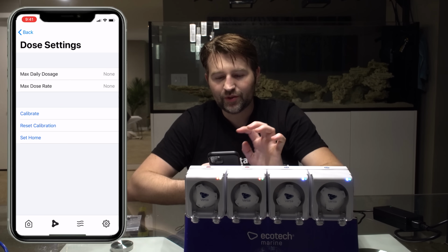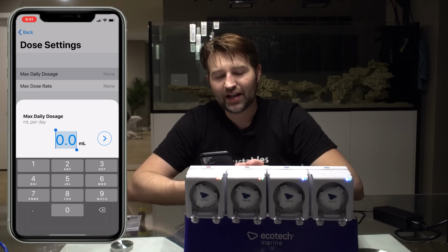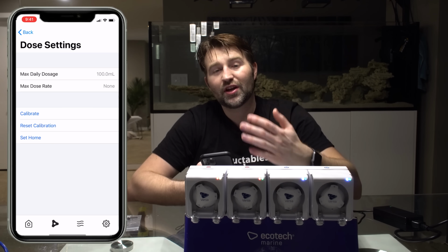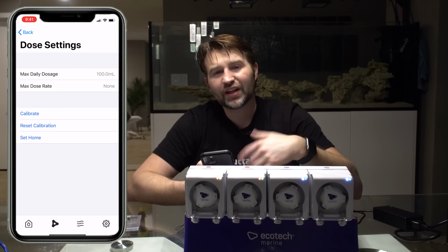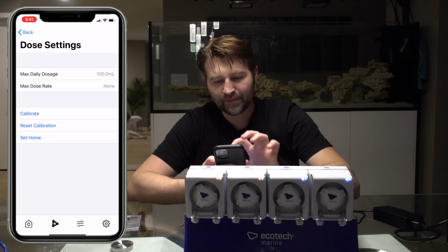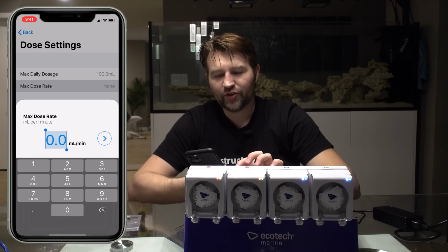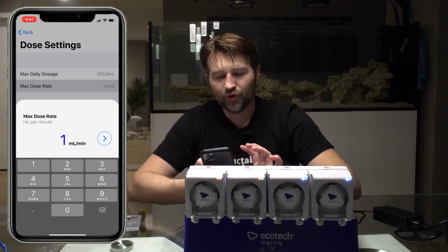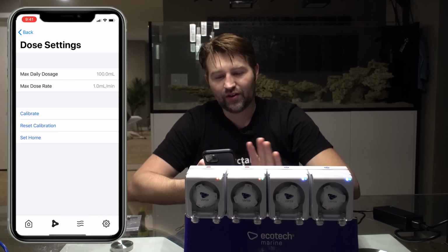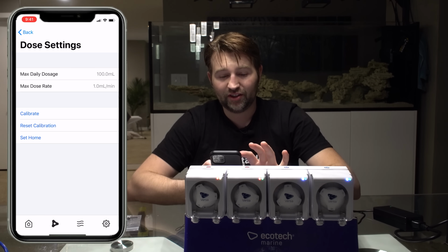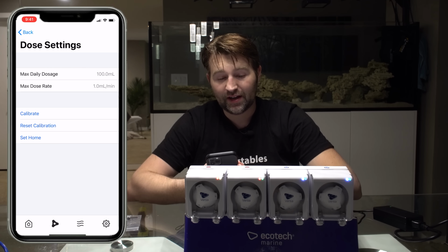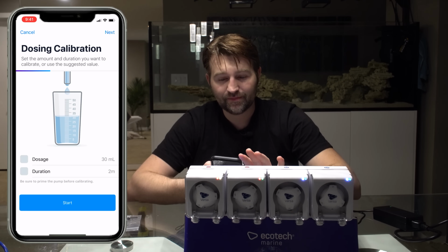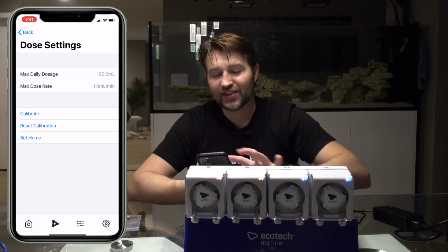Max daily dosage. So if you say you only want to dose a maximum of 100 mils, then you know that pump's not going to dose over it. So it's kind of a safety feature so you wouldn't overdose. And for the dose rate, if you wanted to force it to go at a certain speed, you could say, okay, only dose 1 mil per minute. Now this is going to be super duper slow. Obviously we've got our calibration. We did come with the calibration cup, that's actually sitting on my desk still.